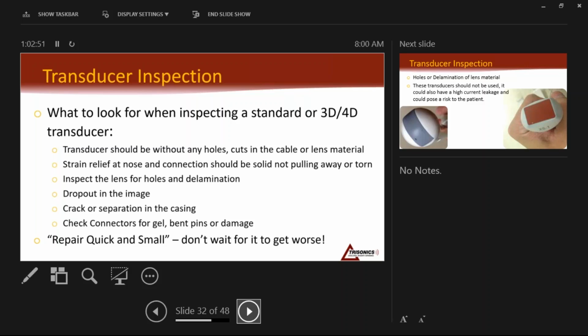So, things to look for now, because part of taking care of the transducer is also finding the problems when they are small and getting them taken care of. We've said for years, repair quick and small. Don't wait for it to get worse. There are a few conditions where we would tell you, well, what's going on with that probe and where it's headed, it can't be fixed anyway, you might as well use it until it dies. If that is the true plan, just make sure that that's the plan. It's probably best to talk to somebody that would really know. Don't assume that you should wait on everything. Most things, we would tell you, as soon as you get a little crack, even a nick in a lens, you're better to replace that as opposed to letting it get worse.